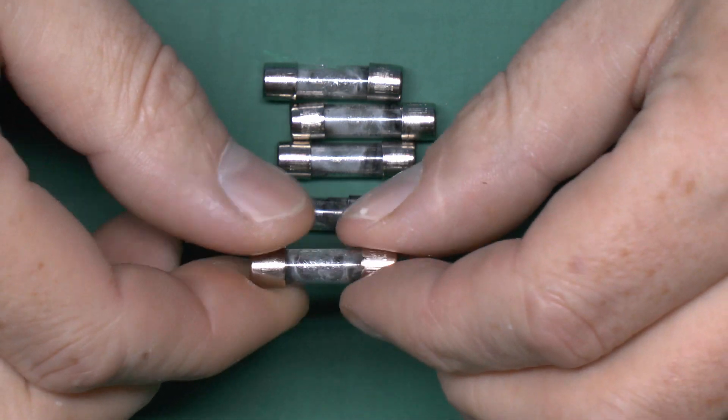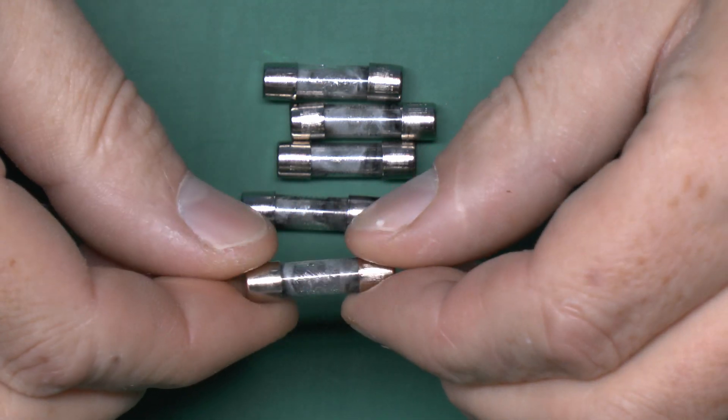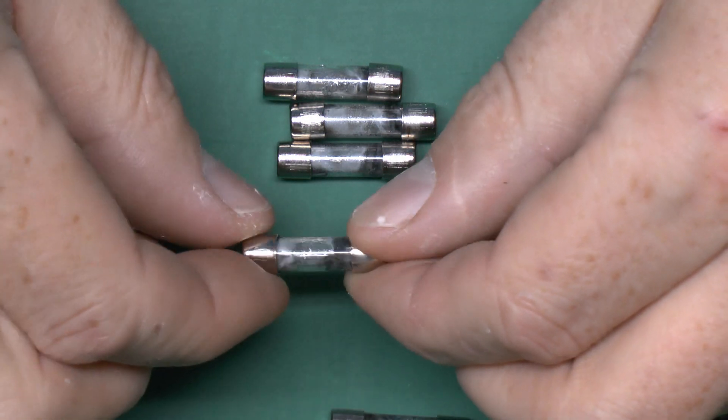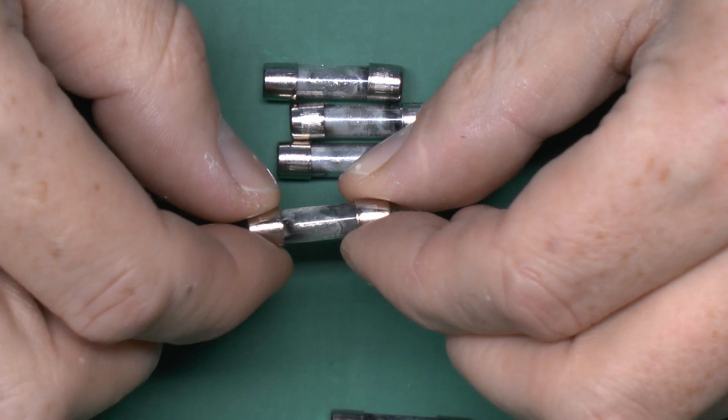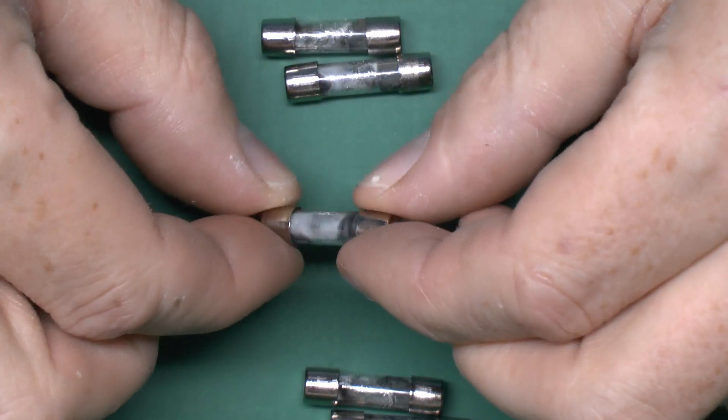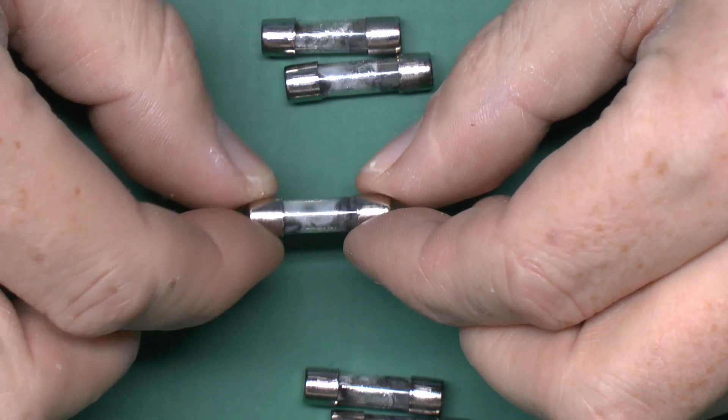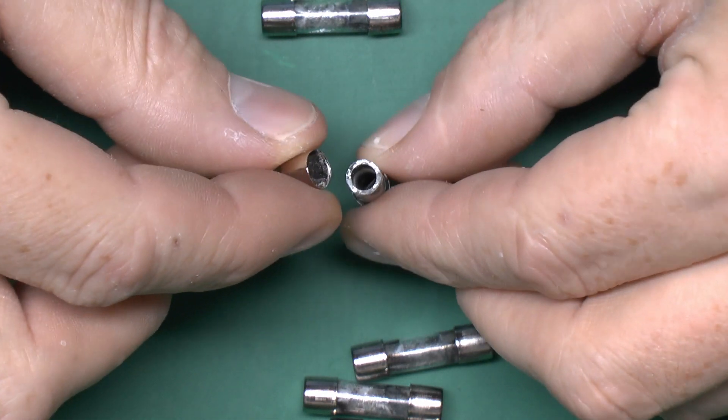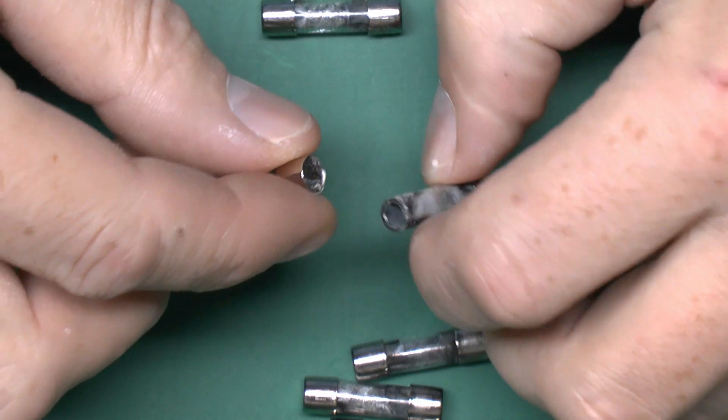But most of them aren't too bad. I mean this one is reasonably still intact there. As is this one. They've all got various degrees of splattered wire on the inside. And again that one's almost the same. Sort of a whitish deposit on that side and more black on the other. This particular one the end has actually come off. So of course you can see inside there's nothing left in there.